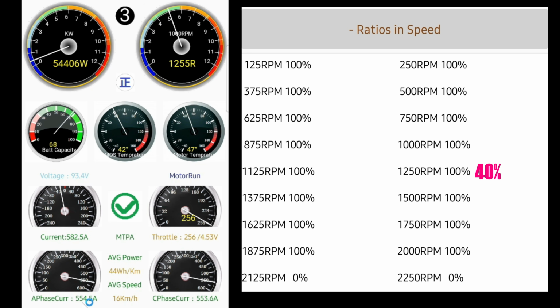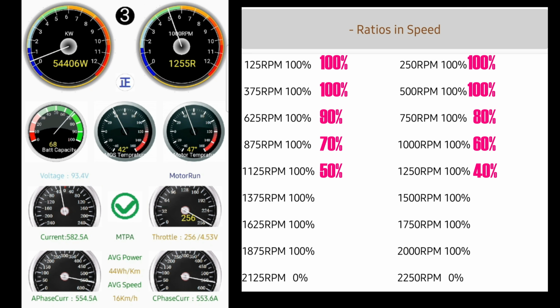Then I could step it back down. It looks like the steps are 1250 RPM. I could put 40% in there, put 50% at 1125, put 60% at 1000, put 70% at 875, 80% at 750, and 90% at 625. You might think I'm limiting power in the lower RPMs, but if we go back and look at them, let's take an example, 500 RPM. And you can see I'm only pulling 622 phase amps. So even at 500 RPM, I don't need 100% phase amps in ratio and speed.